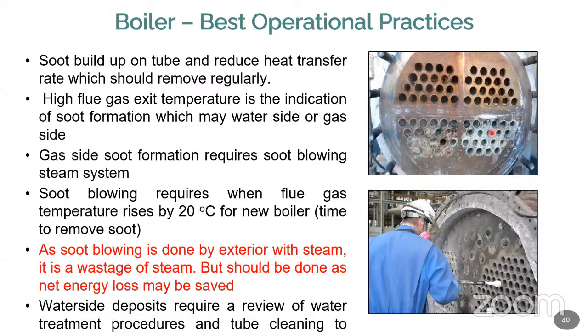So soot formation is going to be one of the important parameters, and it builds up on the tube and reduces the heat transfer rate, so it should be removed regularly. Probably on a weekend or every week or once in 50 days, you have to properly clean it. So a high flue gas exit temperature is the indication of soot formation. It's a very simple idea. When the flue gas temperature is very high, then automatically the boiler tubes and pipes have soot formation. So that is a simple indication.